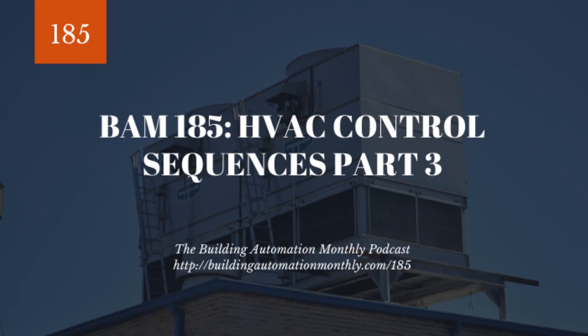And so 90 degrees with 90% relative humidity is a much larger amount of moisture. And the problem with moisture is, one, it impacts the ability for the evaporation effect. When you're blowing air across a human body, you have the evaporative effect, and the evaporative effect removes moisture off the skin of the body, which causes people to feel cool, which is also a reason why you start to dry out if the humidity level is too low and your skin starts to chap, because too much moisture is being removed from your body. So ideally, we're in the 50% to 60% relative humidity range to maximize that evaporative effect.